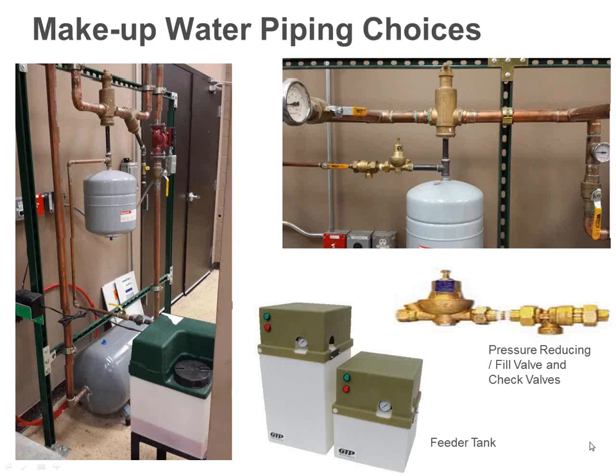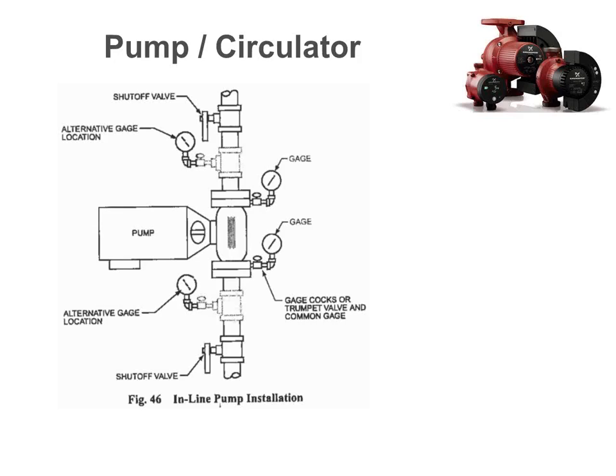Typical circulator piping, minimally, you want to at least have a shutoff valve on the discharge side of the circulator going to the system. It'd be great to have one on the supply side also. Okay. Minimally, though, I don't like walking in boiler rooms and seeing no valves on the system. That's just going to cost you time and labor later if you have to work on something.